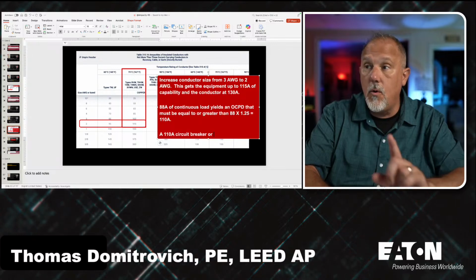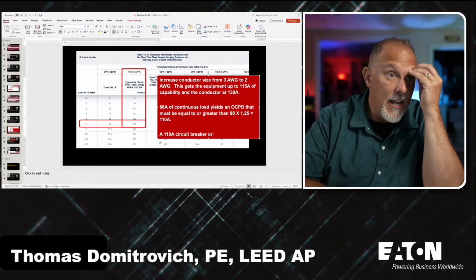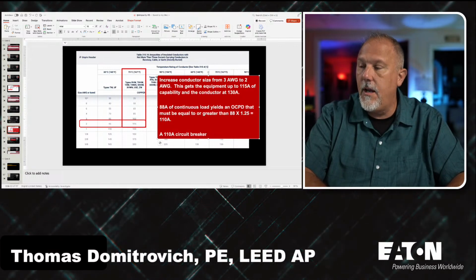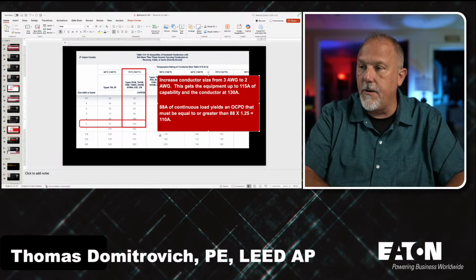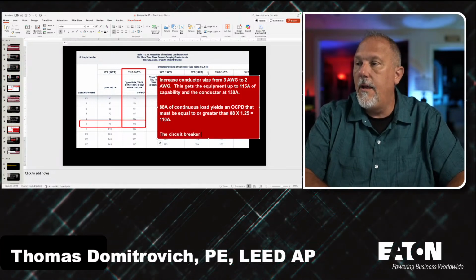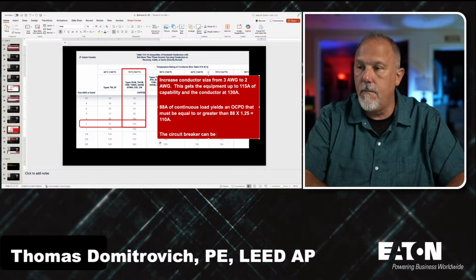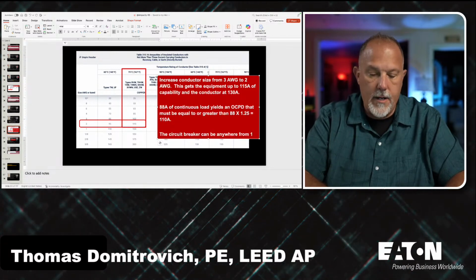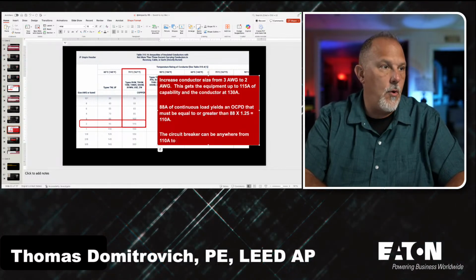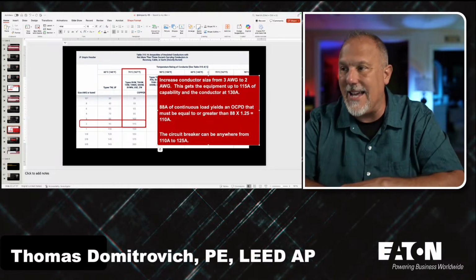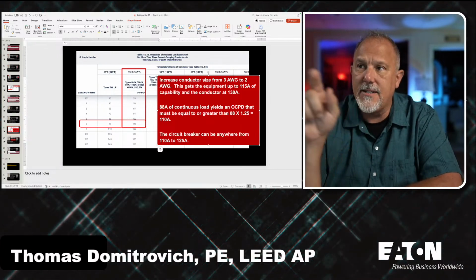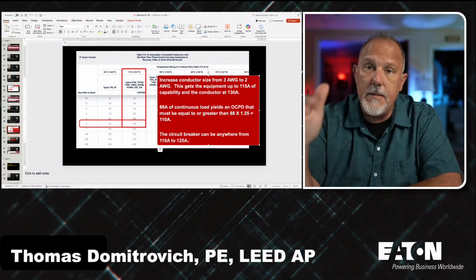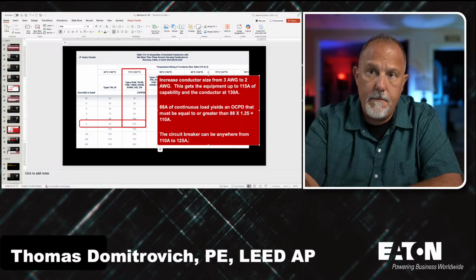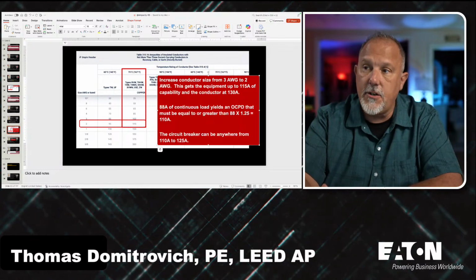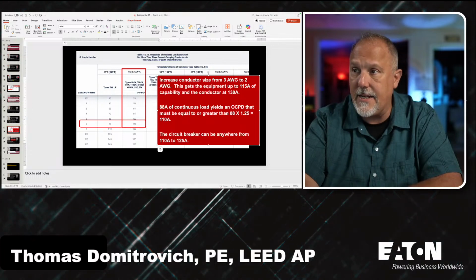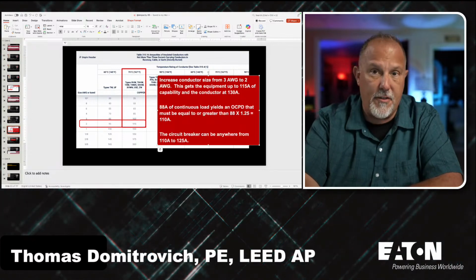Because I have 115, I could use 110. The circuit breaker can be anywhere from 110 amps to 125 amps. And why is that? 110 amps is less than 115. But that's the minimum I need, 88 times 1.25. It's less than the ampacity of the circuit, and much less than the ampacity of the conductor, which is up at 130 amps.